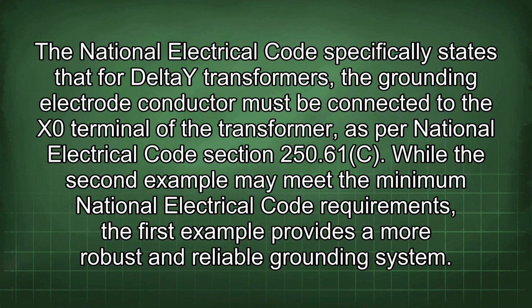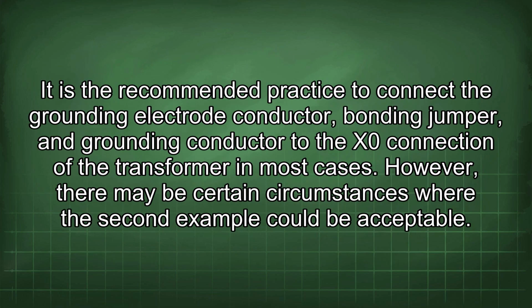250.61c. While the second example may meet the minimum National Electrical Code requirements, the first example provides a more robust and reliable grounding system. It is the recommended practice to connect the grounding electrode conductor, bonding jumper, and grounding conductor to the X0 connection of the transformer in most cases.